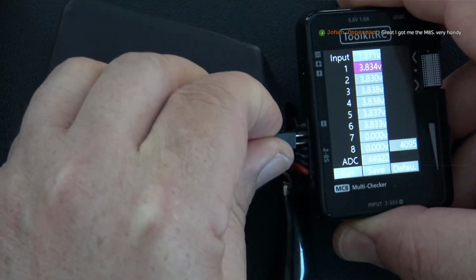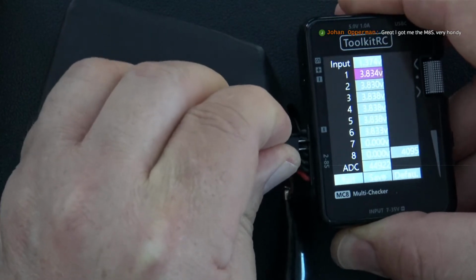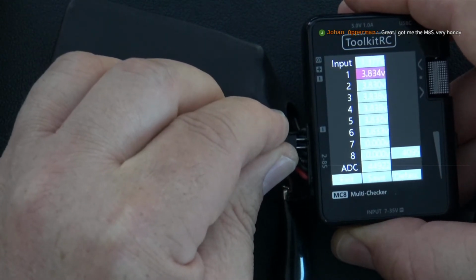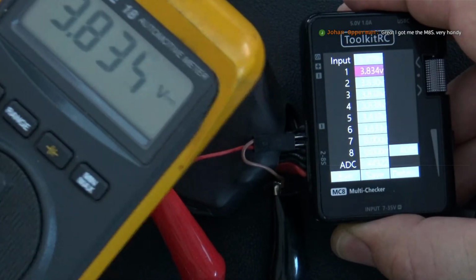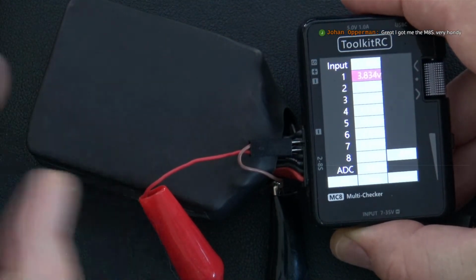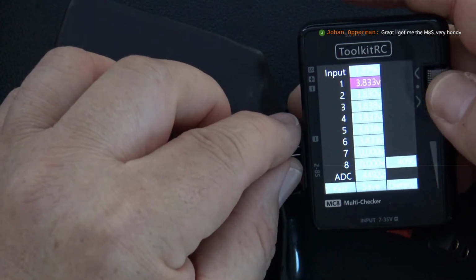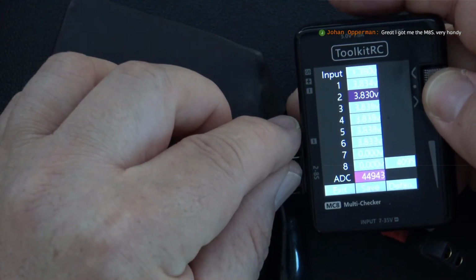That's it - all you have to do to calibrate is take your probe out and move it down to the next pair of battery or balance leads, plug it in, and get a reading. On this one my multimeter says 3.835, and on number 2 it says 3.83, so that one needs a little adjustment.